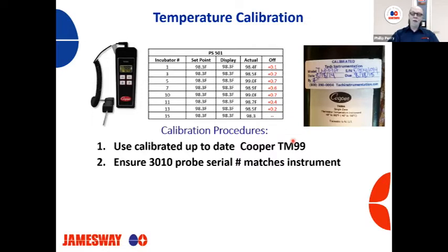Every instrument and probe are married together, so you always want to keep those two together so that you get the correct reading. A different electrotherm with a different probe from another electrotherm can have a different value when you take your reading. I remember one time I visited a hatchery and I asked to see their electrotherm. Well, they handed me a bucket of probes, literally a bucket full of probes, and one electrotherm.